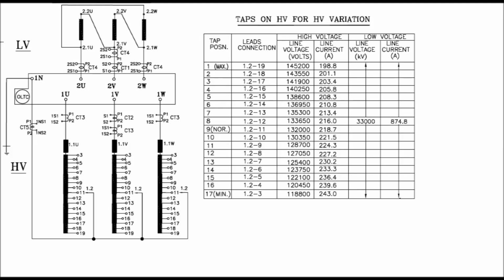Again, for minimum tap position, that is at 17 number tap, the lead connection shall be at number 3 position. So in this lead connection or tap position 17, the minimum tap winding will be selected, and here the line voltage for HV side shall be 118.8 kV and line current shall be 243.0 ampere.